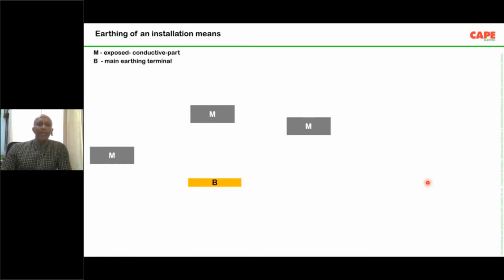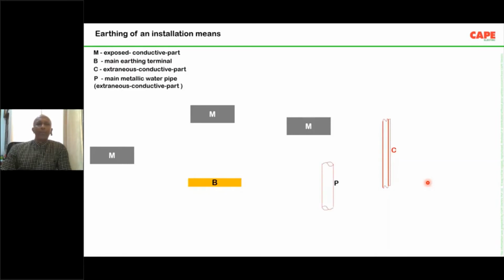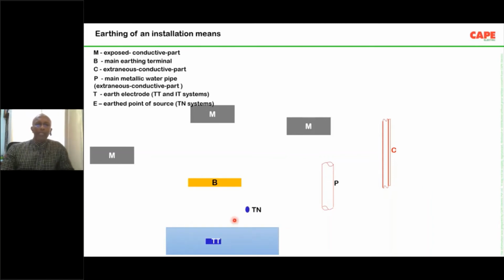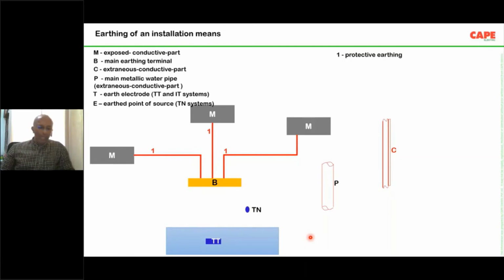Now, in the installation in your building, you are supposed to have a main earth terminal, item number B. You have the extraneous conductive parts, such as structural steel, for example. Then you have a metallic water pipe. Then you have an earth electrode in case of a TT system, and then you have a TN system. TN, this dot means this is the neutral of the transformer or neutral of the DG. The first one is called protective earthing. Protective earthing means connecting all exposed conductive parts to the MET of the building, and connecting extraneous conductive parts to the building. This is called protective equipotential bonding.